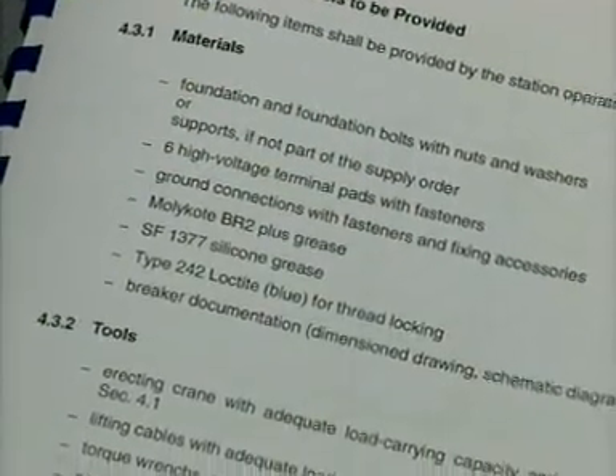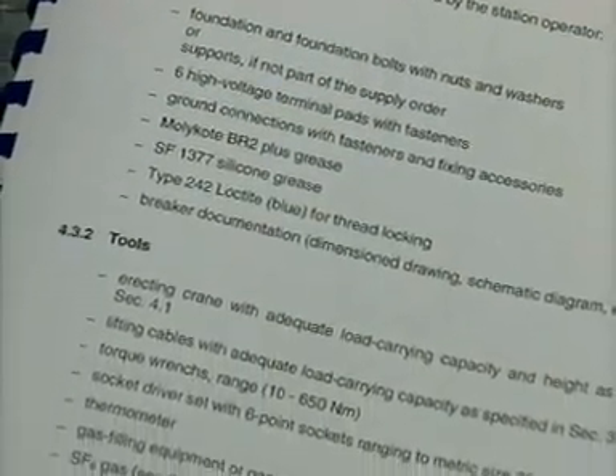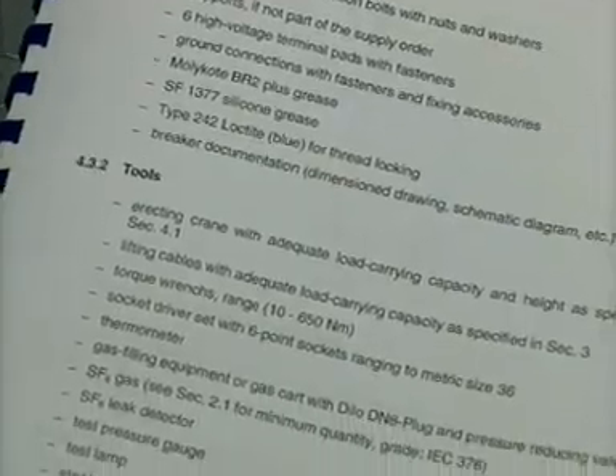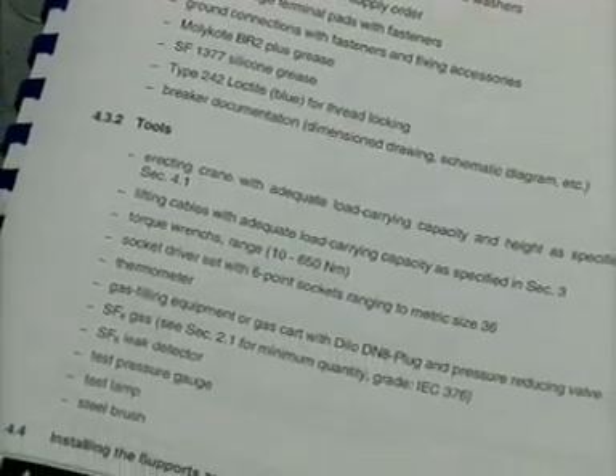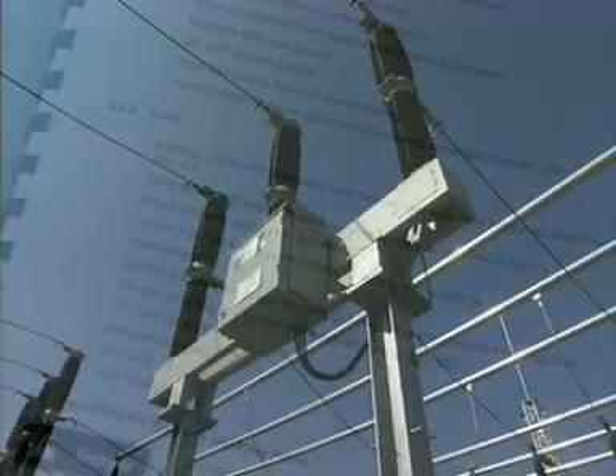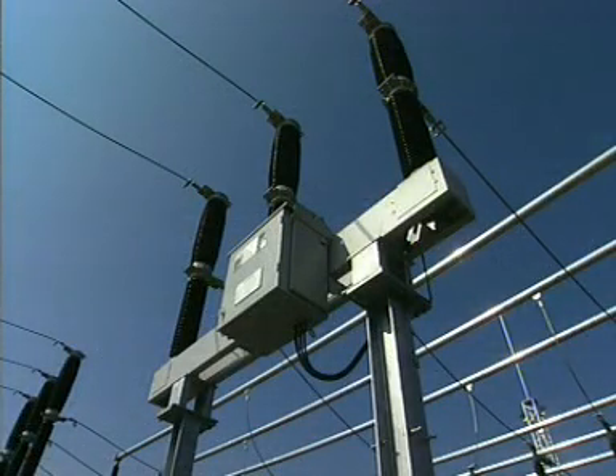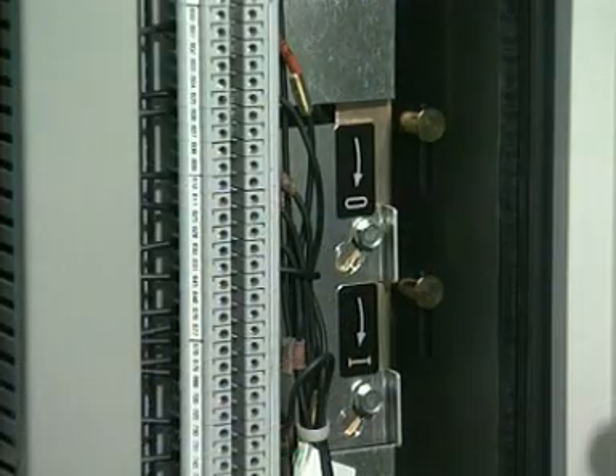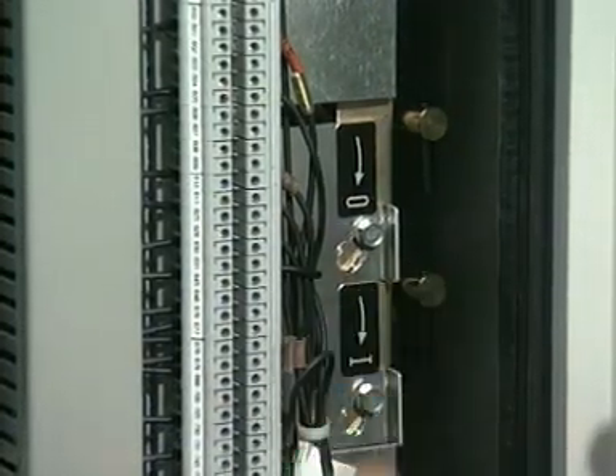The materials, tools, hoisting gear and other supplies that need to be provided by the station are listed in detail in the operating manual. Before any repair work is carried out, isolate the breaker at the station end, ground it and disconnect it from the high voltage network. Turn off the supply voltage and the control voltage. Then discharge the closing spring by carrying out a closing and opening operation manually.